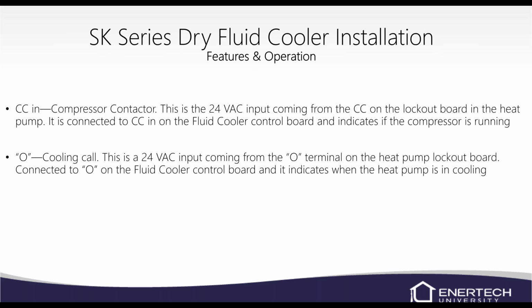CC in is your compressor contactor. This is a 24-volt input coming from the compressor contactor on the lockout board in the heat pump. It's connected to CC on the fluid cooler board, and basically it tells the fluid cooler when the compressor is running. It's a 24-volt signal to the board. Whenever it sees O, it realizes that that is a cooling call, and it's coming from the O terminal on the heat pump lockout board. And it'll be connected to the O on the fluid cooler. Again, indicates that it's in cooling mode.